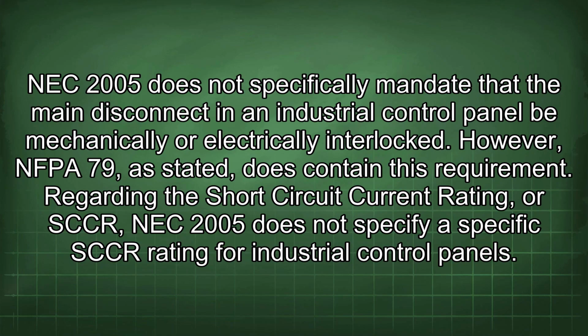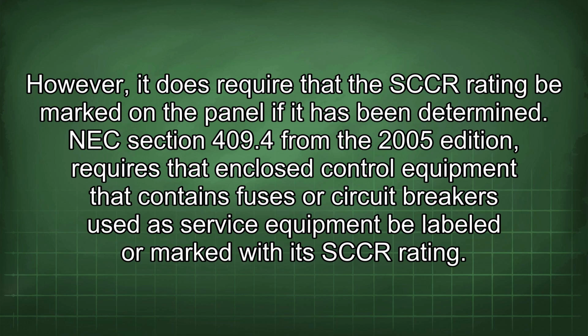NEC 2005 does not specifically mandate that the main disconnect in an industrial control panel be mechanically or electrically interlocked. However, NFPA 79, as stated, does contain this requirement. Regarding the short circuit current rating, or SCCR, NEC 2005 does not specify a specific SCCR rating for industrial control panels. However, it does require that the SCCR rating be marked on the panel if it has been determined.